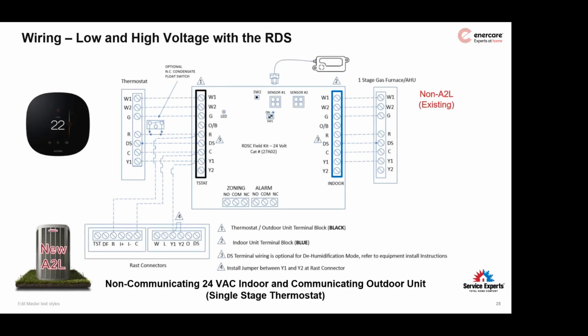Next example. Same idea, we're going to pair a new A2L piece of equipment. Specifically, this is one of the variable units because it has the RAST connectors. But we're going to pair it with a pre-existing 24-volt system. So the indoor unit is still one of those legacy units, we'll call it an EL296 from 5-6 years ago. It's paired up with a 24-volt thermostat. And we're bringing in a new variable heat pump or air conditioner that's A2L equipped. So now this one is the 24-volt version. It's not the communicating version.